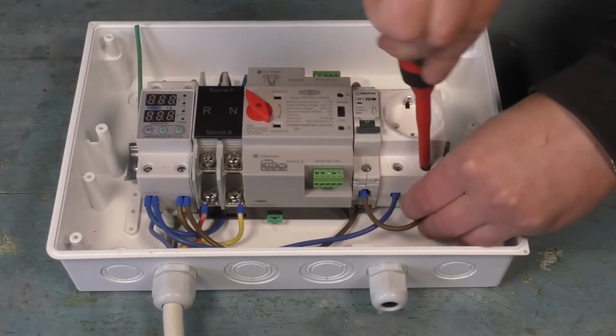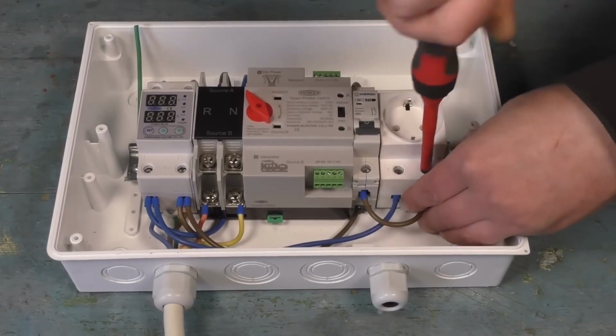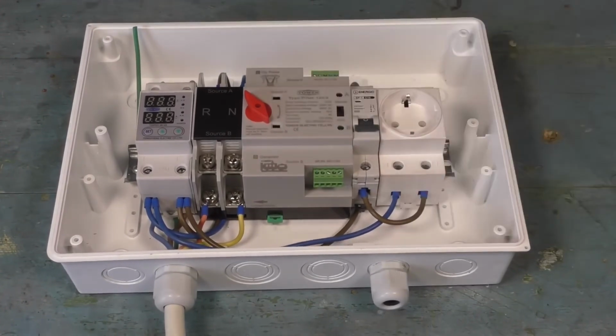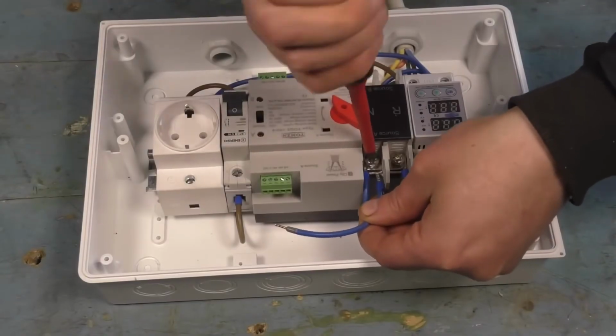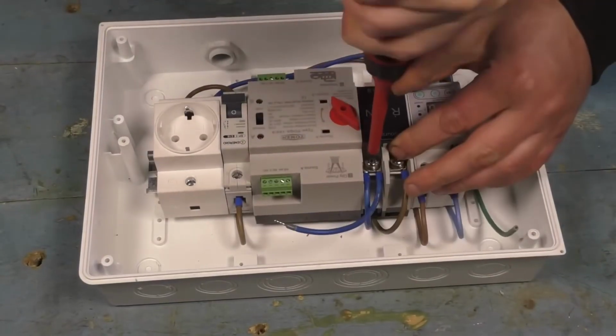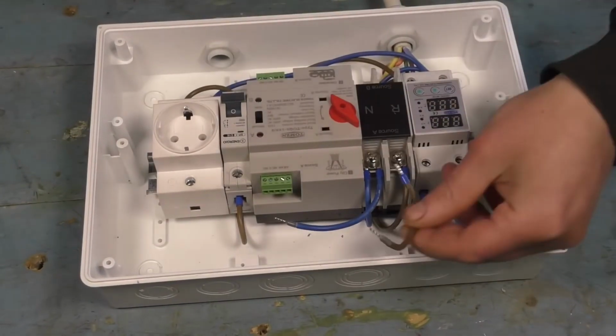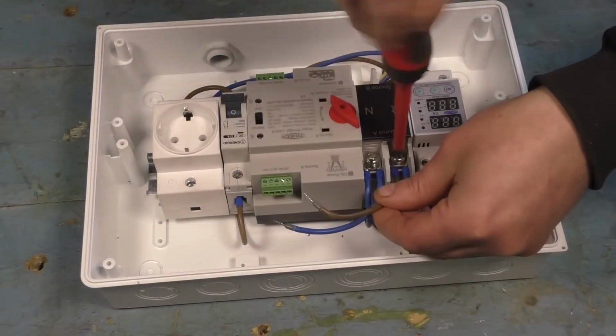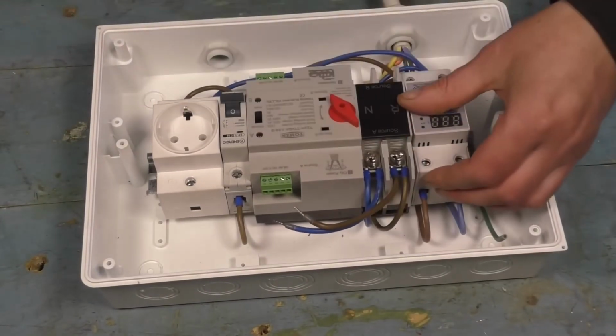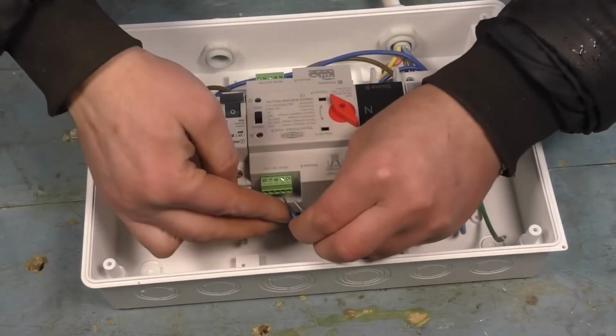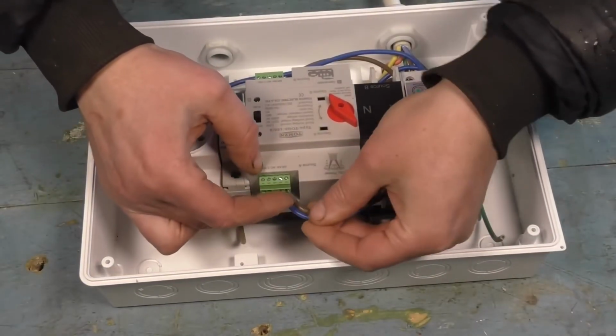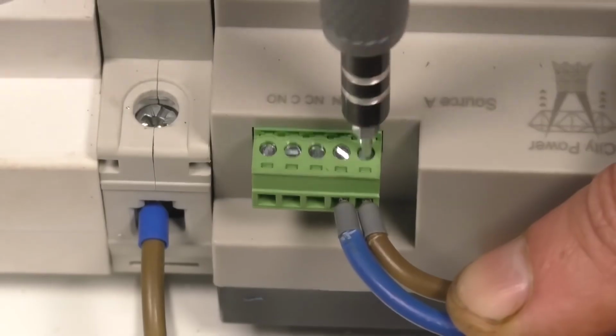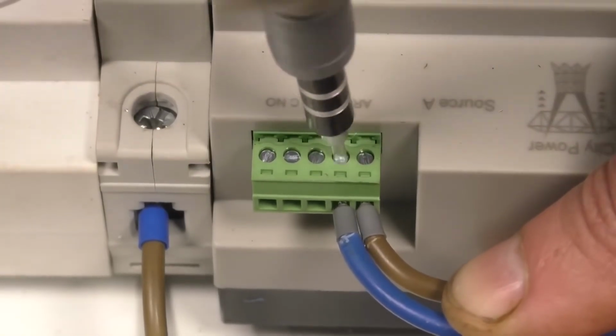We connect the output of the circuit breaker to the socket, and in this way it will work with protection. Next, you need to install 2 jumpers at the input and connect terminal N to terminal AN and terminal R to terminal AR. On the Thomson circuit breaker, everything is labeled, so if you do it yourself, you'll easily figure it out. I'm showing everything clearly so you can see exactly what to connect and where.